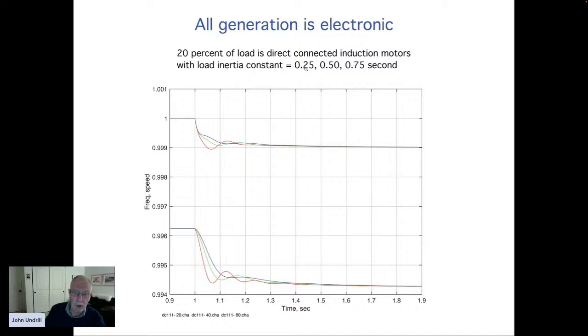This would be an induction motor driving a cooling water pump somewhere. The diameter of the pump and the characteristic of the pump is smaller physically than the diameter of the motor. This would be induction motors driving high-speed compressors, where the inertia of the driven load, the compressor that the motor's driving, is greater than that of the motor itself. The frequency dip is affected by the thing that the motor is driving. The motor speed itself, of course, is less than the synchronous frequency because we're talking about induction motors. But again, as you have a low motor inertia, you have a slightly faster rate of decrease of frequency.